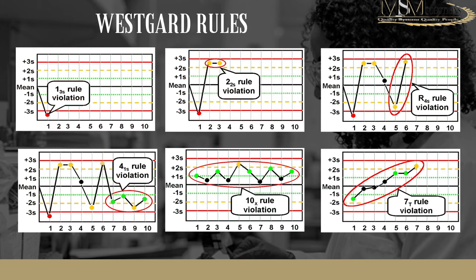The last rule is the 7T rule violation: when you have seven points in either an increasing or decreasing pattern, that is also a violation. You can see a clear trend — either increasing or decreasing — with seven points consistently moving in one direction. This often signals something wrong with your system, such as a QC material depreciating and needing a fresh batch, instrument contamination, or another issue causing drift.